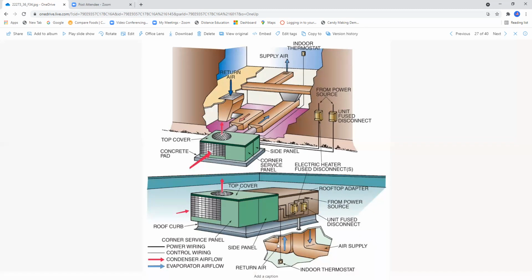And of course, you have your supply ducting and return air ducting. The big thing about package units on the roof and package units on the side is that it's extremely important to seal that ductwork, because we don't want to air condition the outside of the building or heat it in the wintertime. The ductwork has to be integral, has to be tight, has to be very well designed and waterproof. And very importantly, make sure that you have your disconnects for the equipment so it can be serviced.